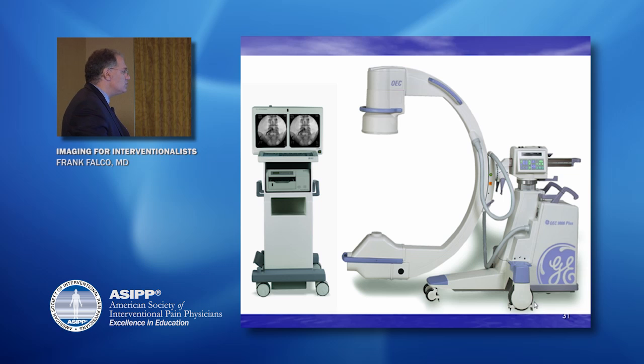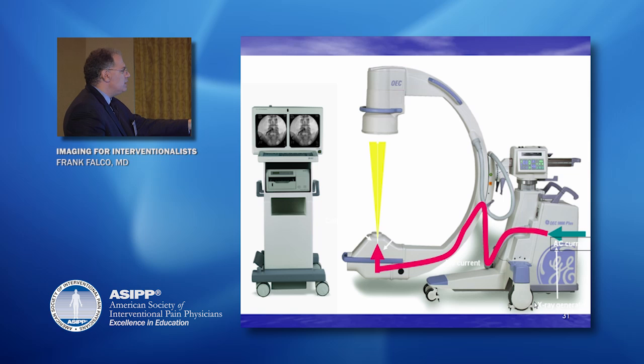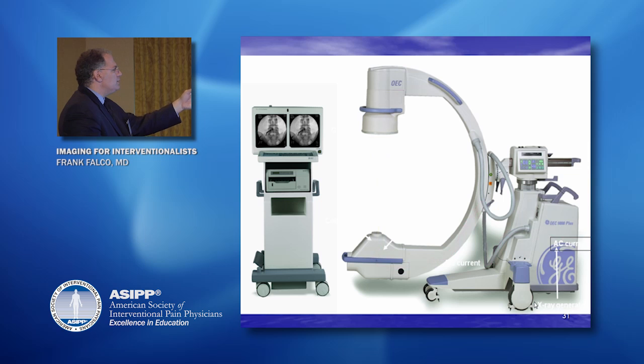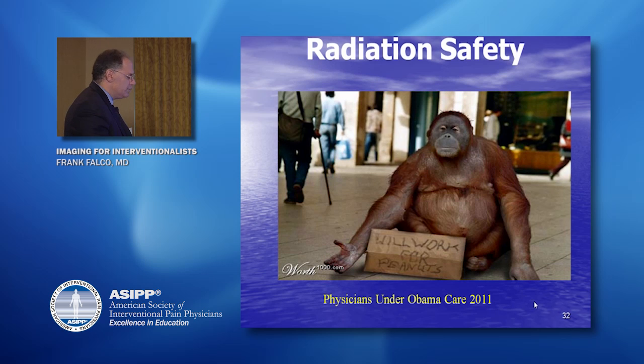So here, this looks like an OEC 9800. So you're plugged in here. Here's the X-ray source. This is in white, and I changed it last night into black, but you're not going to be able to see that, unfortunately. But there's that. Here we have our anode and our cathode. This is where we're creating our X-ray beam. So AC current comes in, it comes here. We create the X-ray. Phosphorus is created, and the OEC, or the image intensifier, creates a bigger signal. That gets sent over to the fluoroscope there on the left side.